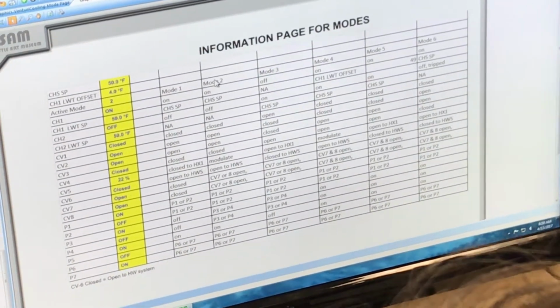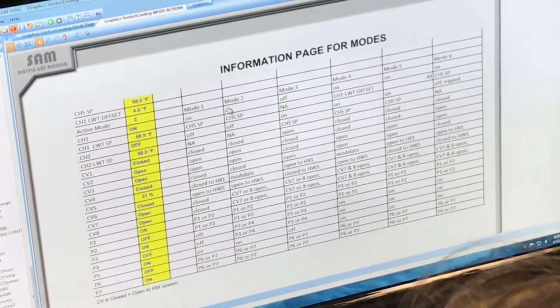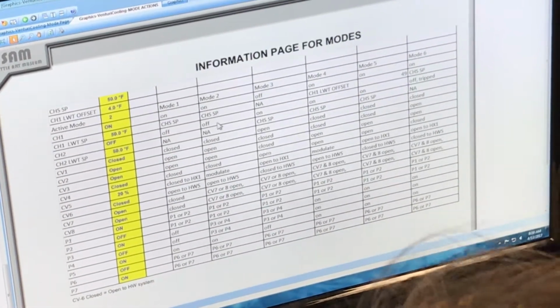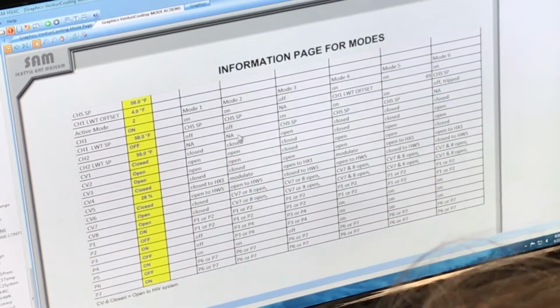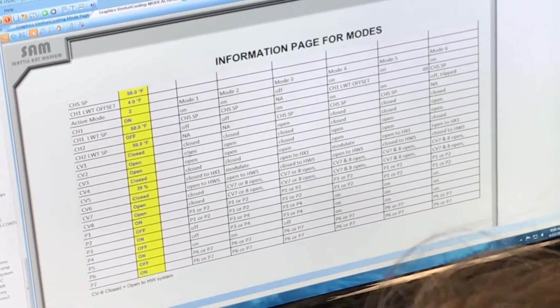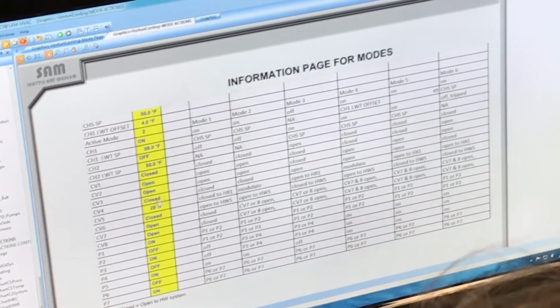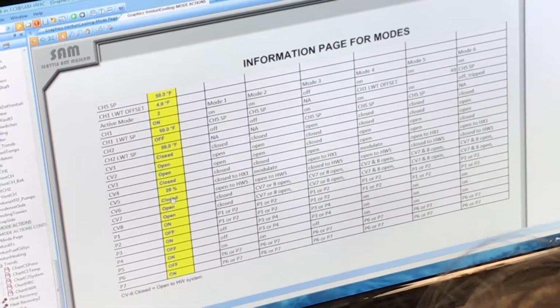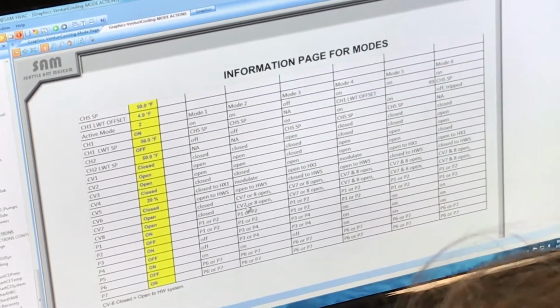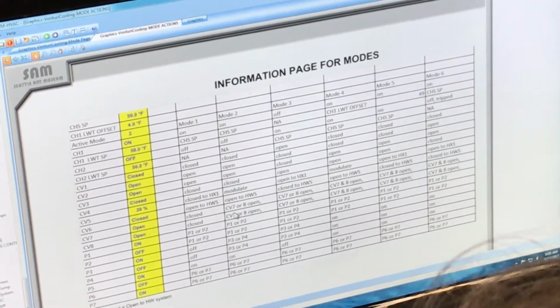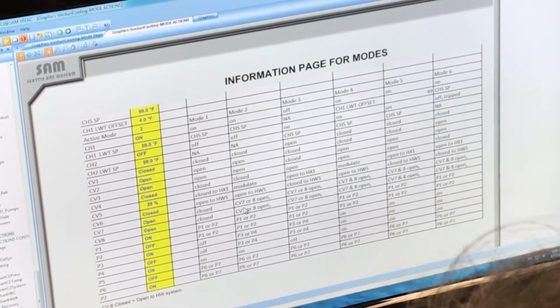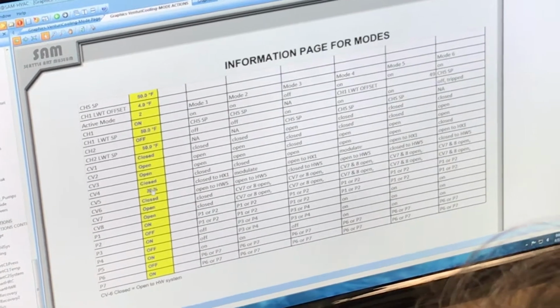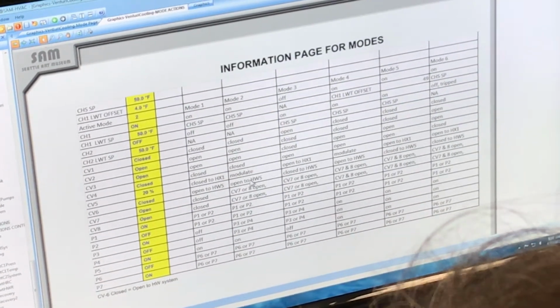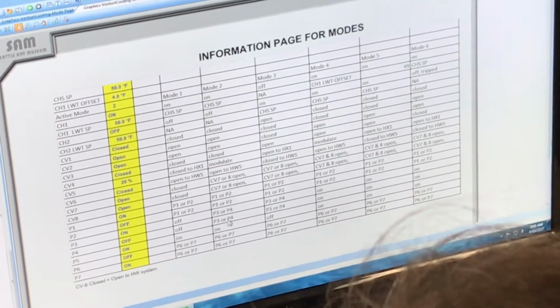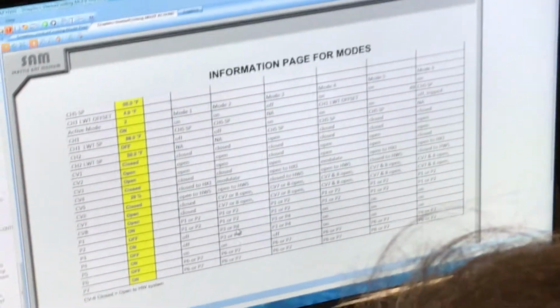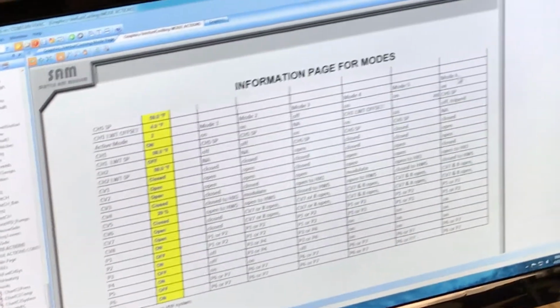So mode 2, this is supposed to be on. It is. Set point is 50. This is supposed to be off. It's off. Doesn't matter. Close, close. See how this is working? Open, just open, close, match. Match these things to make sure that everything is working properly. And you can see with mode 1, it says close to HX3, and then mode 2 says modulate. So closed would be 0. You're seeing it at 29% right now because it's modulating, so don't let that fool you. When it says modulate and you see a percentage there, that's what you're supposed to see. If it's closed, it's going to be 0.